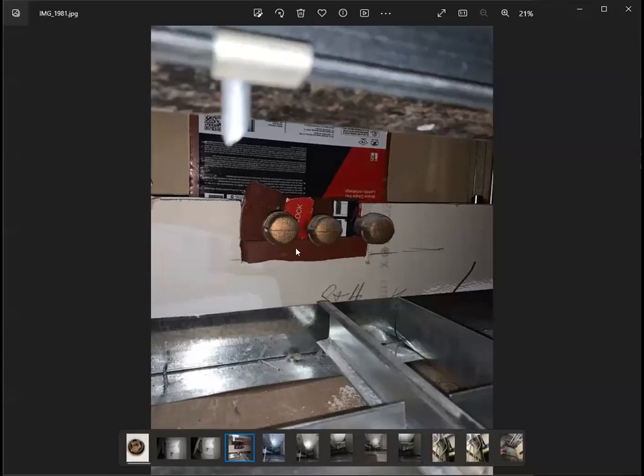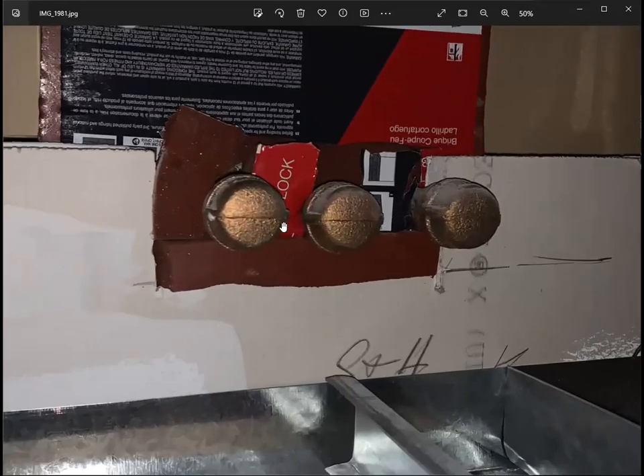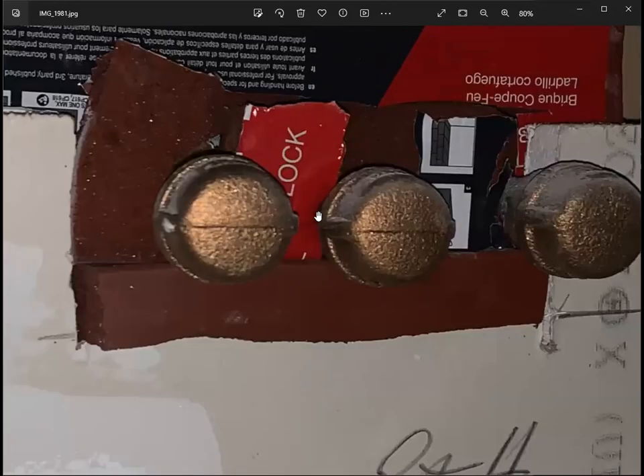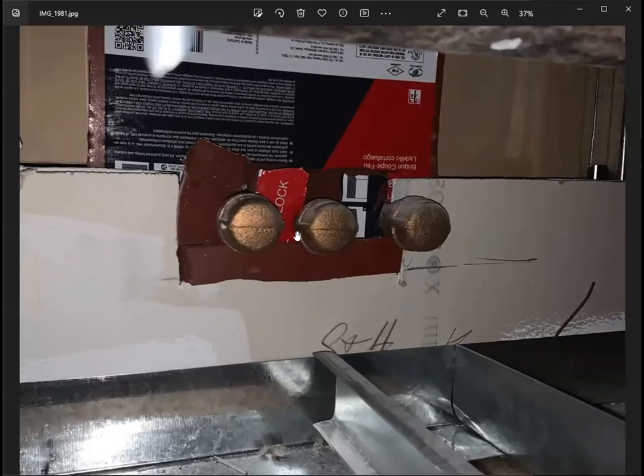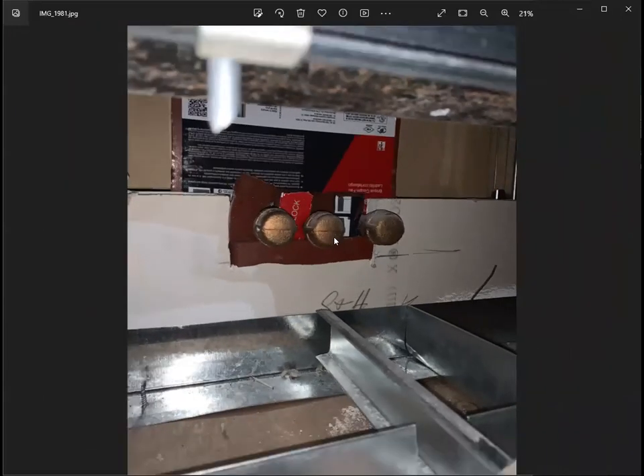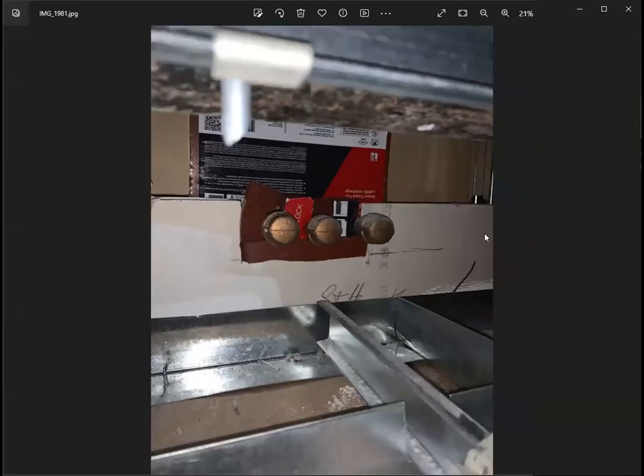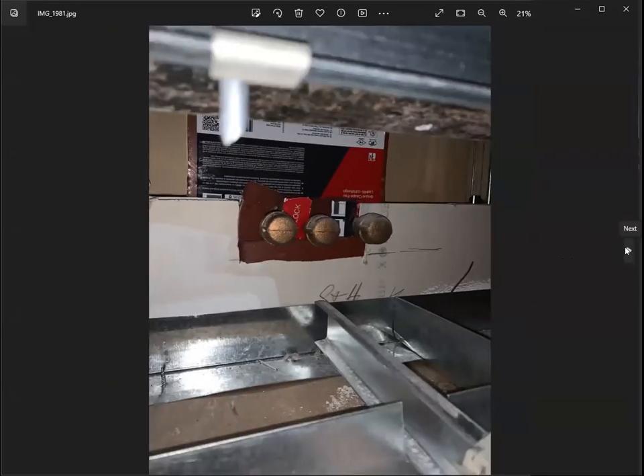This is a fire blocking situation, fire stopping. I believe this wall is new, and they probably just put some sheetrock or gypsum board, so they closed out an opening just to retain the fire rating of the wall. All those pipes are fire stopped. As you can see, there is some fire blocking material, but you need to have a caulking material applied around it. So I believe this is a fire-rated wall.